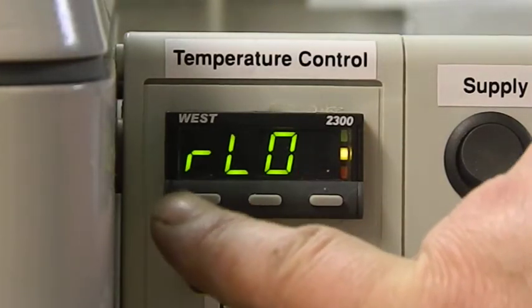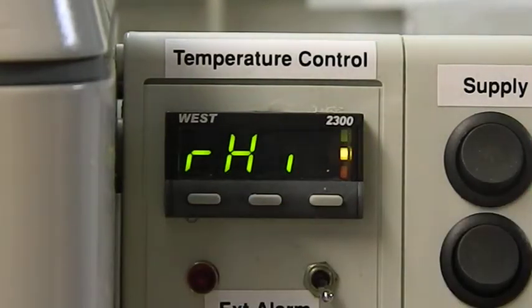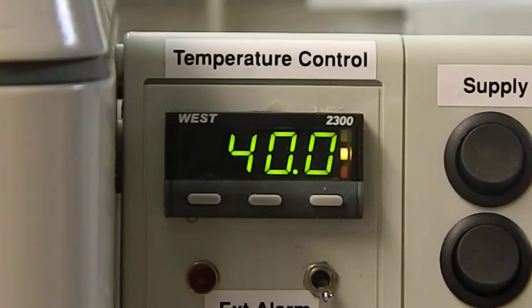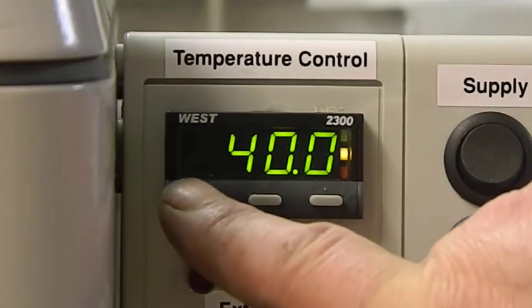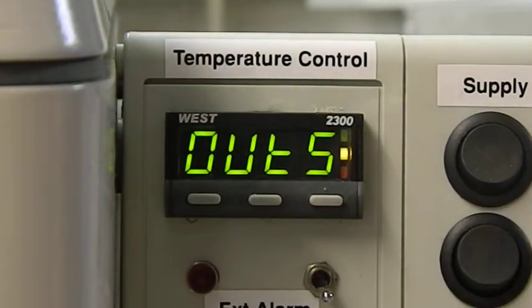Okay, press twice again to get RHI. This is the highest setting the processor will accept, so 40 degrees is the maximum temperature you can set the machine to. Left one twice again. OutS, this tells the controller where the outputs are configured.